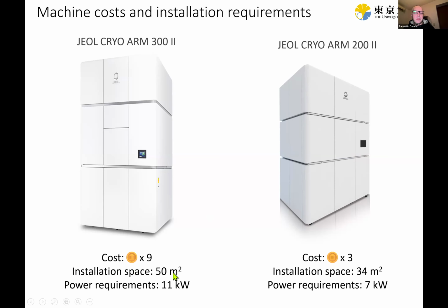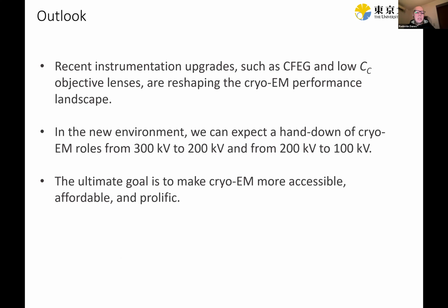Installation space is typically about 1.5 times larger, I guess. Power consumption is also about 1.5 times higher. And the service costs, which I don't know about, are, I guess, 2 times or so higher for the 300 kV. So considering all this and the difference in performance that we show with the highly optimized 200 kV machine, I think in the near future we can start to see some shifts or reshaping in the cryo-EM performance landscape. Thanks to the cold FEG and the low chromatic aberration objective lenses, this could happen.